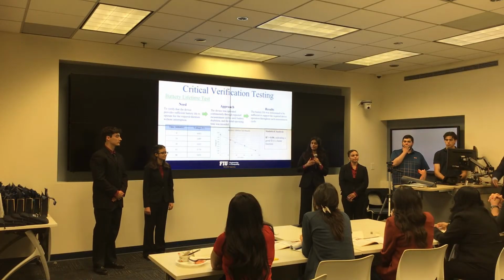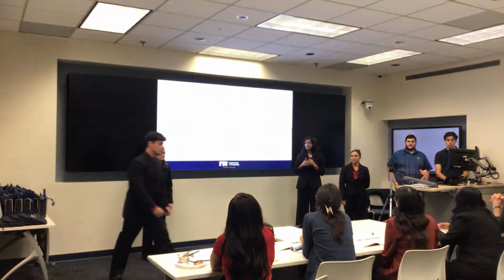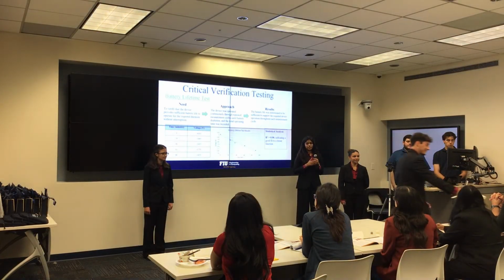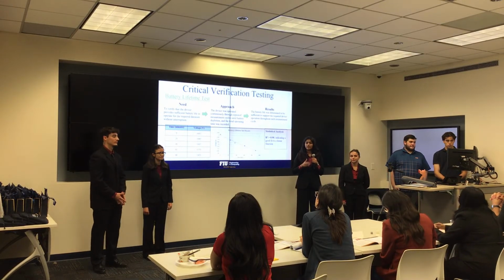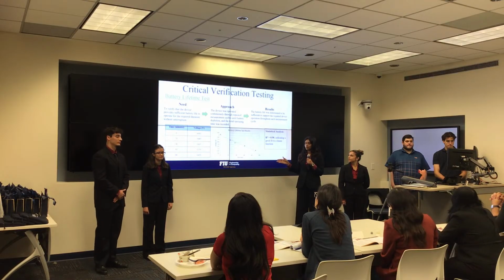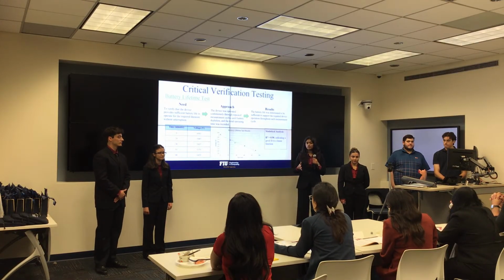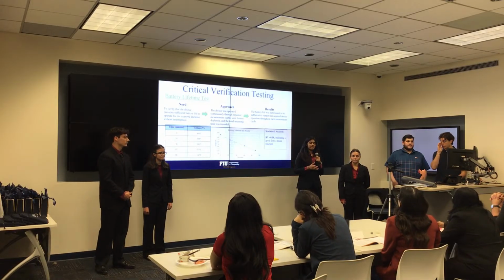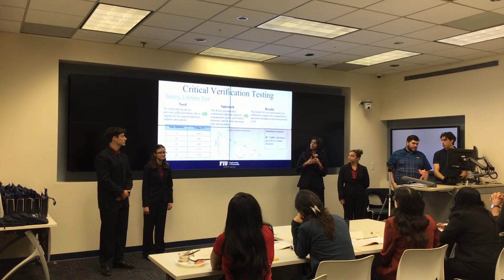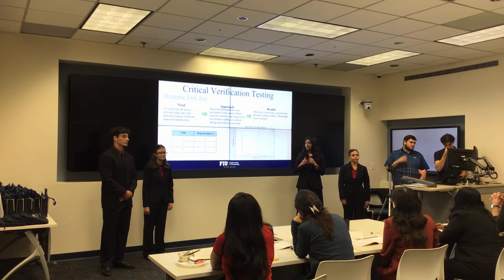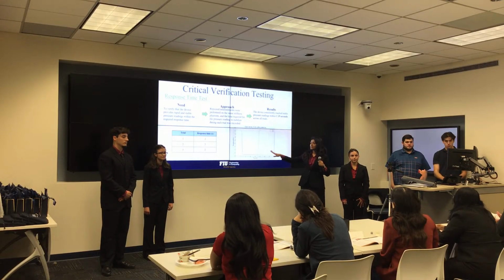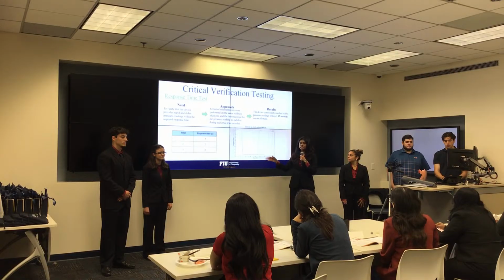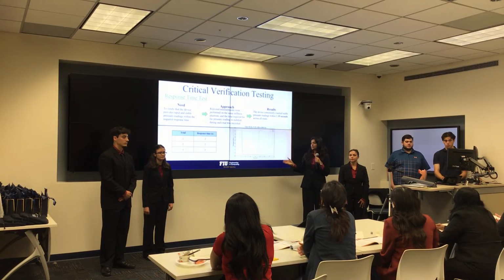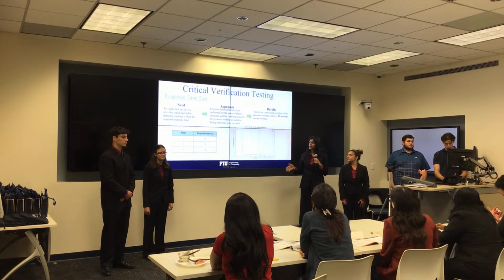Moving on, we did the battery lifetime test, where we let the device run continuously until depletion and recorded the operation time. Our device showed that it had sufficient battery life and was able to run exceeding the 45 minutes that was the minimum that we set, and gave us an R-square value of over 0.9, indicating that the device ran continuously without degradation. Moving on to our last test, which was the response time test, where we measured how long it took for the device to stabilize the pressure readings. As we can see in the graph, the device was able to continuously stabilize within 15 seconds, indicating that the device was able to provide fast and reliable feedback.